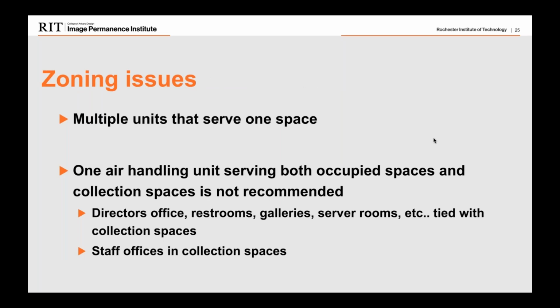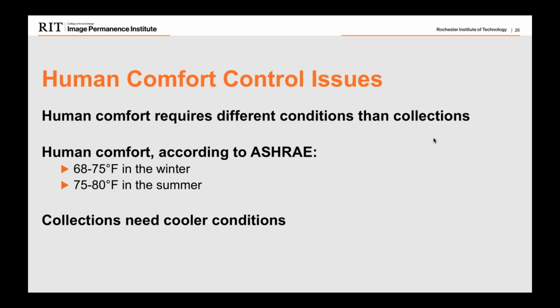Lastly, if one air handling unit serves spaces occupied by both collections and staff, we strongly recommend keeping those spaces as separate as possible if feasible. We've seen many instances where collection spaces are served by the same systems as directors' offices, restrooms, and galleries, and this comes with a major drawback: human comfort issues. You're trying to condition a collection space for preservation at the same time as conditioning for human comfort, which require very different atmospheres. Even one staff member occupying a collection space long-term will shift conditions toward human comfort needs rather than the ideal preservation environment.